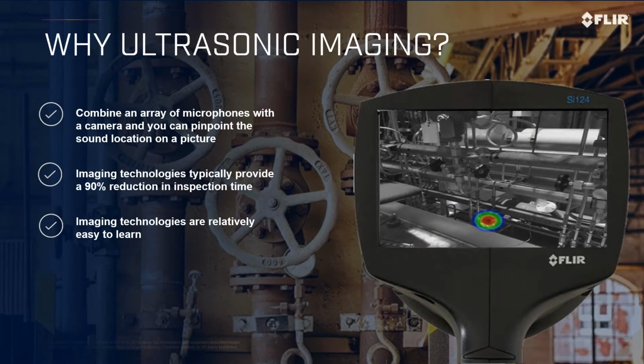So we do this by combining an array of microphones, like I said, with a camera, and you can pinpoint the sound location on a picture. That's what you see right here, this picture to the right kind of blown up, and you have this little rainbow, right? Red on the inside, then green, and then a blue ring around that. So that's how we triangulate that sound. All those microphones are kind of pointing, saying, hey, this is where the source of that is.